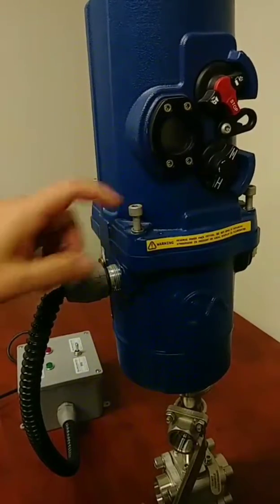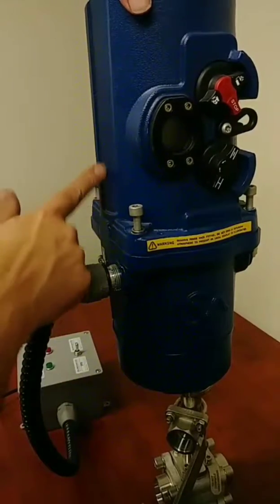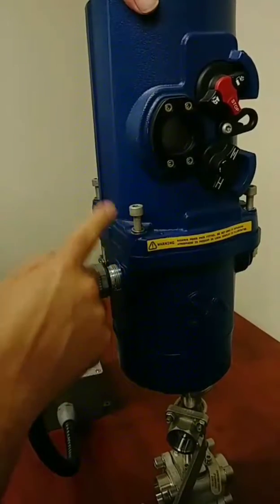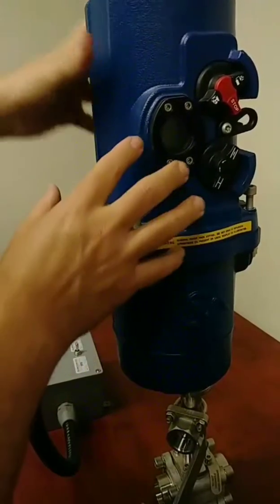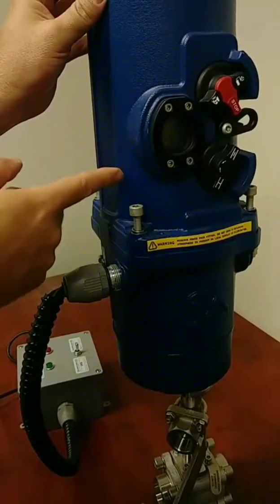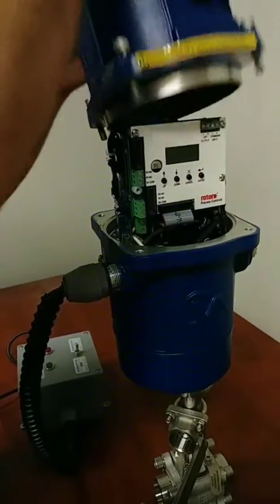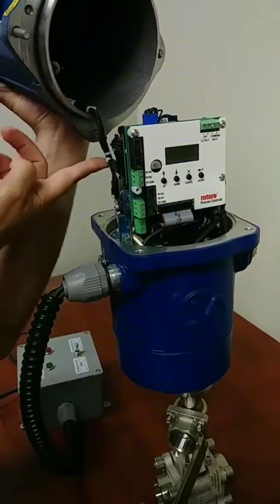I've already loosened these four allen head bolts that hold the cover on, so I'm going to go ahead and lift it off. On this side of the actuator, there's a wiring harness that connects the local display and super capacitors to the main control card of the actuator. I'm going to pull this off and then disconnect the wiring harness by pulling straight up on the connector. I'll hold it up — this is the location of the wiring harness. Pull it straight up and set the cover aside.